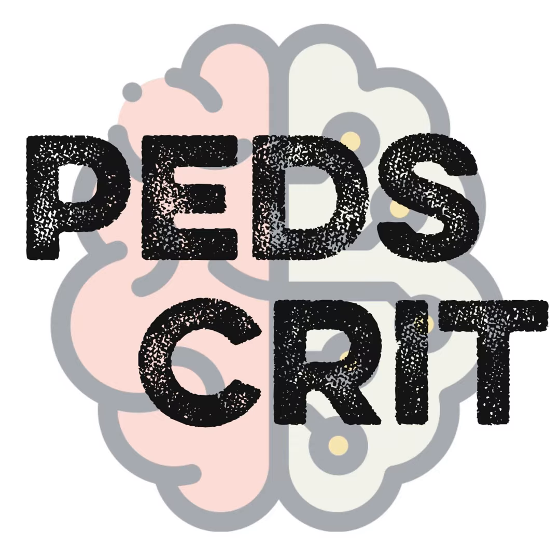Because it's flow and time based, those are the only two variables that you control. There's like a dozen knobs on the front of this machine. Yeah, there are. All they do is influence some aspect of those two variables. The patient's underlying pulmonary mechanics then define the subsequent measured pressures that result from that gas flow over whatever amount of time was spent. For two patients with different compliance, the exact same VDR flow rate and time settings will result in different measured pressures, because pressure is the dependent variable based on what the patient's lungs are doing, not what the ventilator is doing.